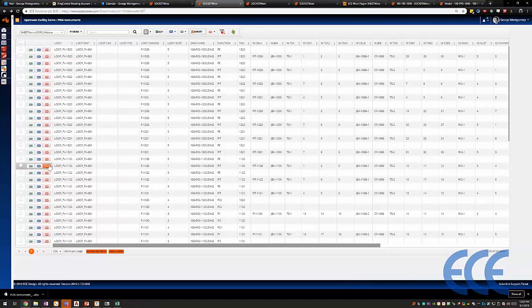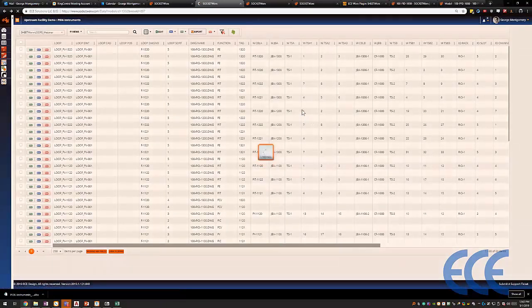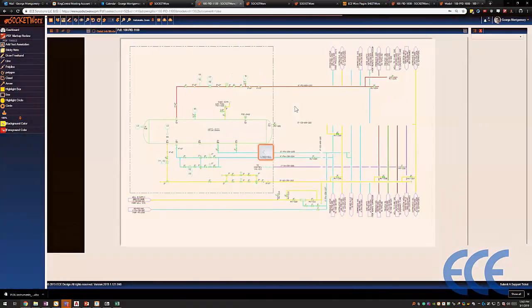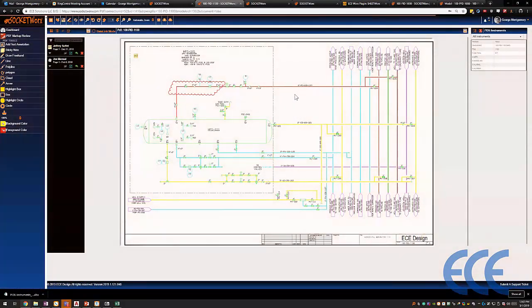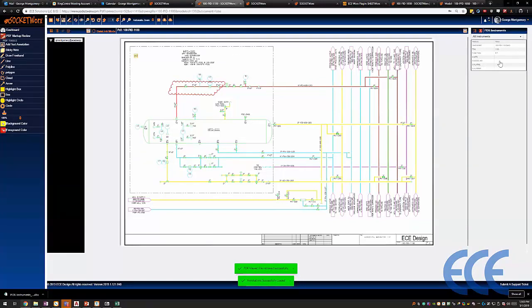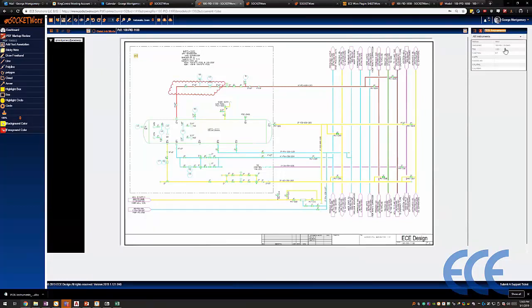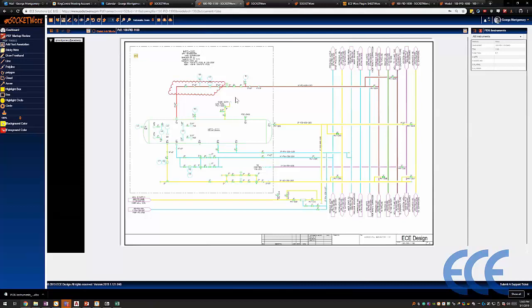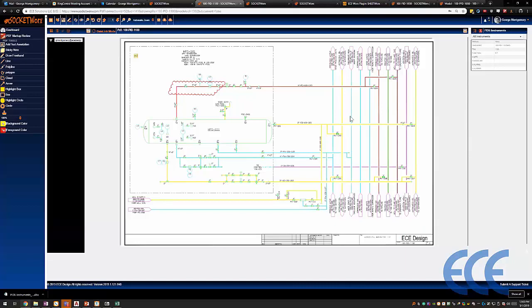If I wanted to take a look at this drawing, this 1100 drawing where that loop is located, I can click this little PDF button. This is going to pull the actual PDF that was PDF'd out by the designer for this project. This PDF contains that 1120 loop that I wanted to read information from. I can see the information here on the right-hand side. So 1120 is the tag, the function is a flow-indicating transmitter. I really don't have a lot of information that the designer put in on the PNID that I can pull from that database. So what I did is I basically took that initial tag and was able to populate additional information that's also stored in the database that I can then create an Excel sheet from and then kick it over to SOCKETWorx.